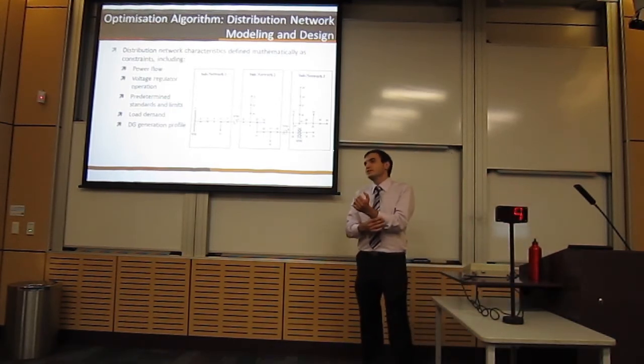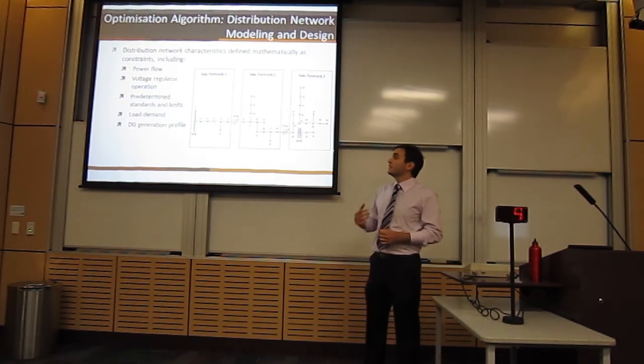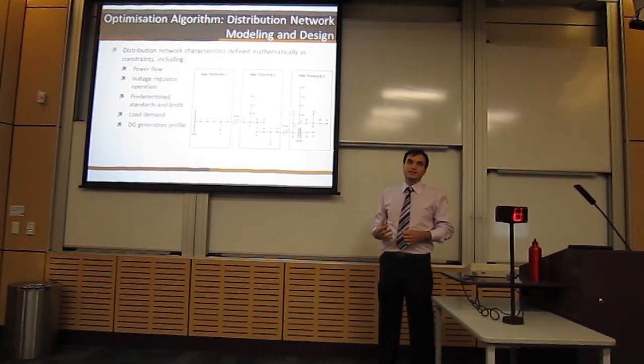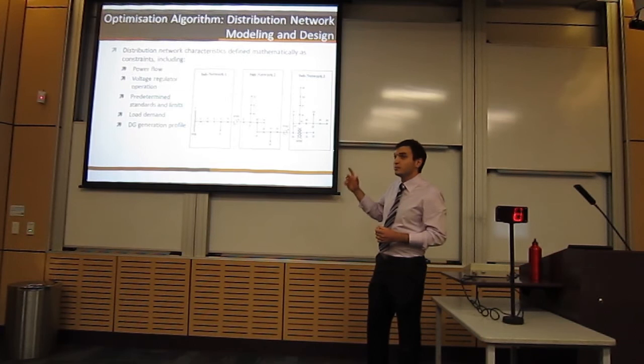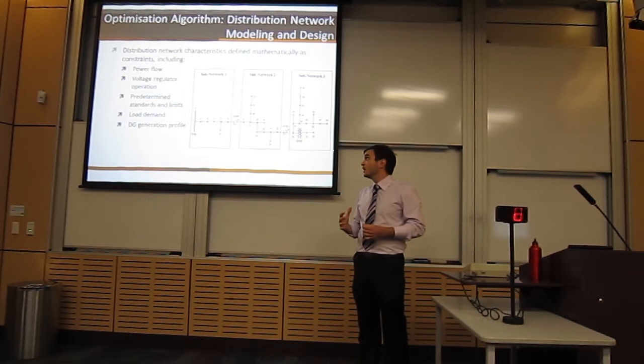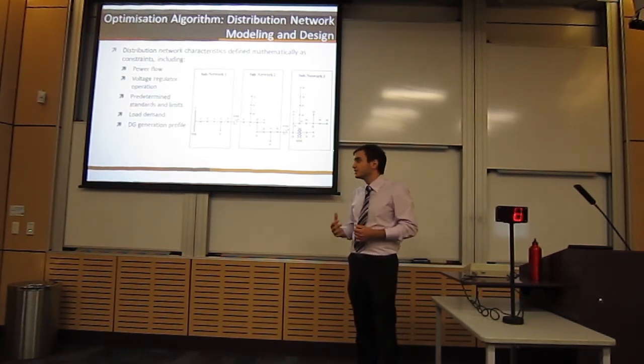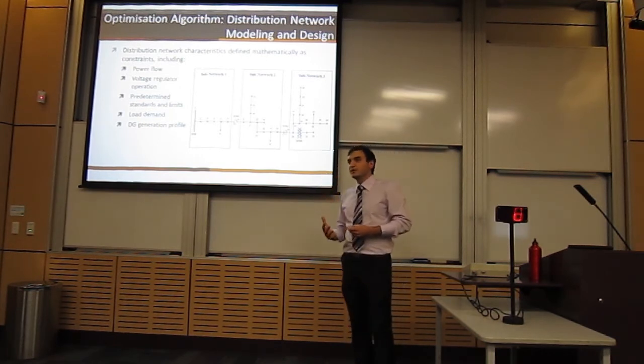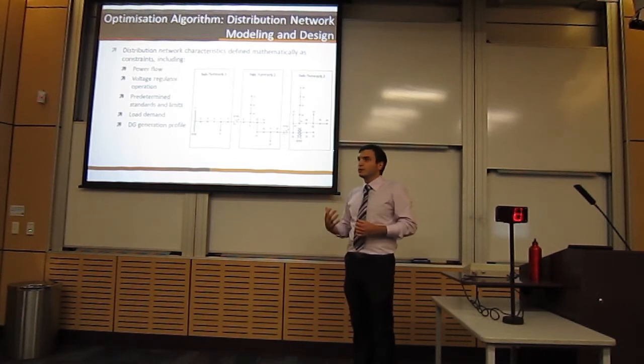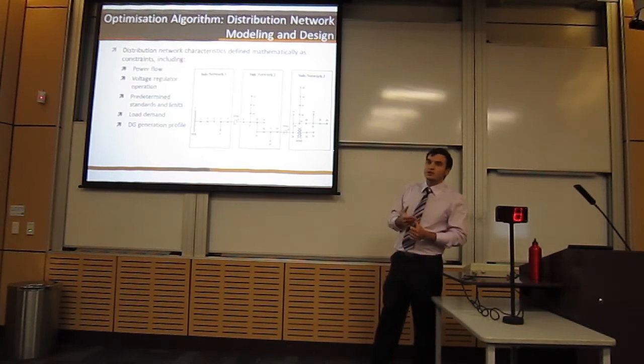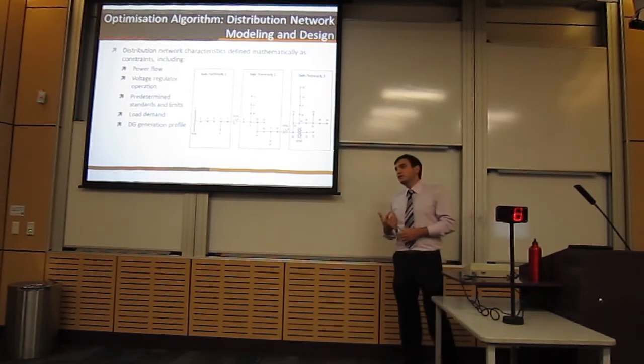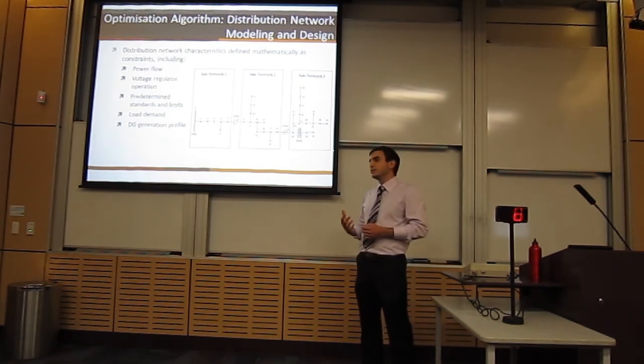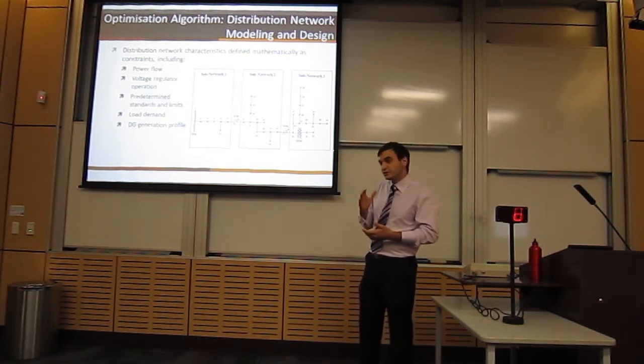In order to ensure that the optimization algorithm correctly modeled the distribution network, the network constraints were modeled mathematically and implemented as constraints into the optimization algorithm. The entire network was split into three sub-networks, each joined by a step voltage regulator. For each network, load flow equations were implemented to determine voltage and real and reactive power at each bus. The step voltage regulator operation was then implemented to join the three networks. Predetermined standards were applied to ensure voltages at each bus were within network standards, and that current capacity of transmission lines and equipment ratings were not exceeded. The time-varying nature of load demand and DG generation was implemented by separating the model into discretized time steps over a 24-hour period.